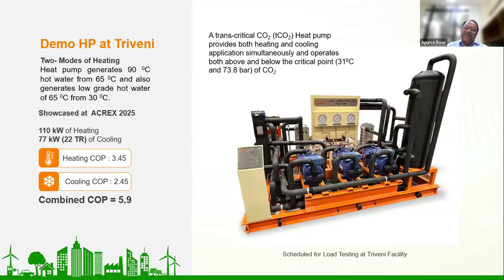And that's what we call a transcritical CO2 heat pump, or in short, TCO2 heat pump. The one in front of you takes ambient water, let's say at 30 degrees Celsius, and gives hot water at 90 degrees Celsius. In between, we have also put in a heat recovery unit, because of which it also gives us 65 degrees Celsius water. I'm talking about this particular unit, and its combined COP is 5.9. It gives 110 kilowatt of heating and 77 kilowatt, or 22 TR, of cooling. Right now, the system is under testing here.